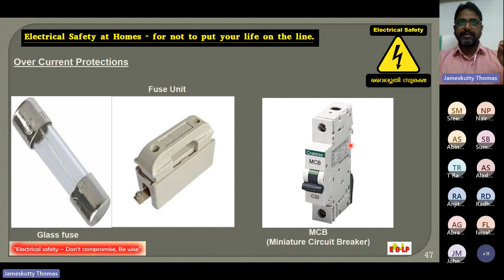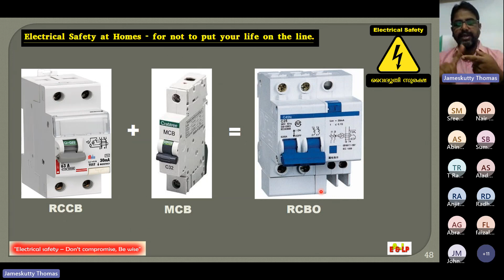But actually we can get a combination of RCCB and MCB. See here, it is RCCB and MCB. RCCB is for leakage protection and MCB is for overcurrent protection. We can get such a combination, which is called an RCBO. So we can get both leakage protection and overload protection with the RCBO.